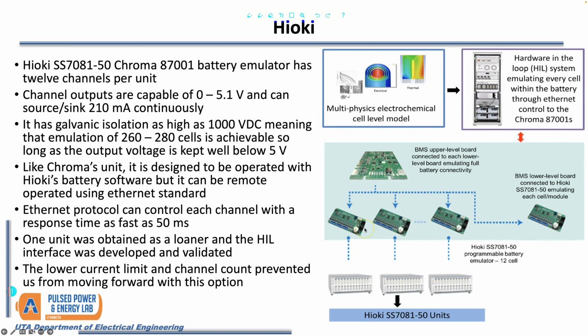The next option we looked at is Hioki. It's very similar to the Chroma, with a similar voltage rating up to 5.1 volts. However, it only has 12 channels per unit, and its current is much lower—it's not capable of 5 amps, only 210 milliamps continuously. It has the 1000 volt isolation, however, and a latency of 50 milliseconds. So it's a little slower, with less current capability and fewer cells per unit.